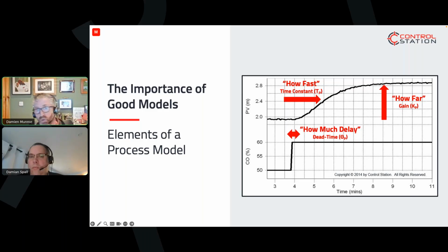The heat has to flow through those steam lines. It has to come through the shell and tube heat exchanger, heat the product in the heat exchanger. The product has to pass out of the heat exchanger to the downstream instrument, and then start to register that value. So it's something that you're always going to have this lag in.